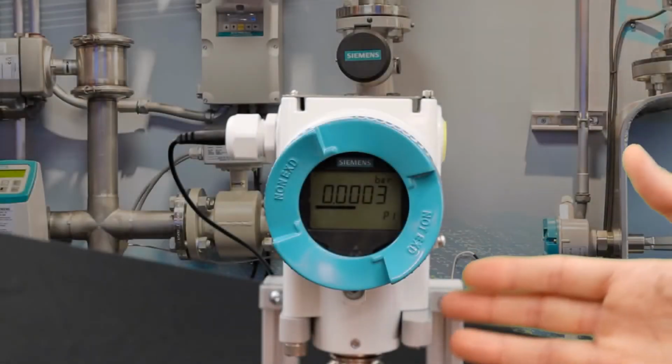Today I'm going to show you how to configure your Siemens P320 420 pressure transmitter for level measurement. A pressure transmitter can be used to measure liquid level inside the tank simply by measuring the hydrostatic pressure above it. That's why the tank diameter doesn't really matter. Today we're going to go over 4 different applications and we'll see how to configure our pressure transmitter for those level applications. Let me first introduce the product itself.